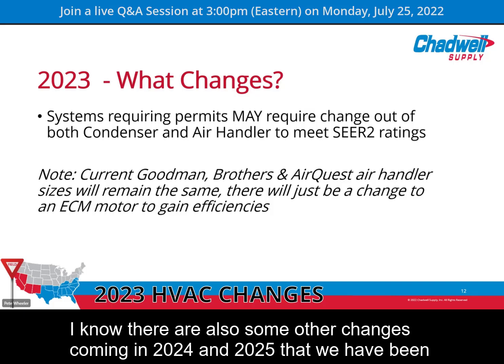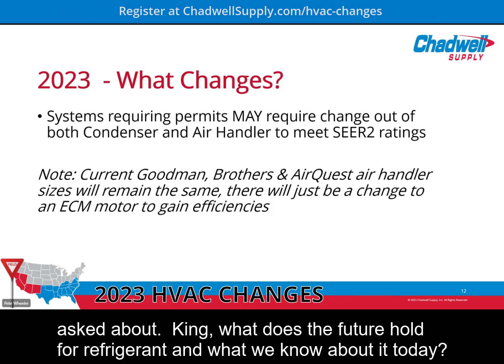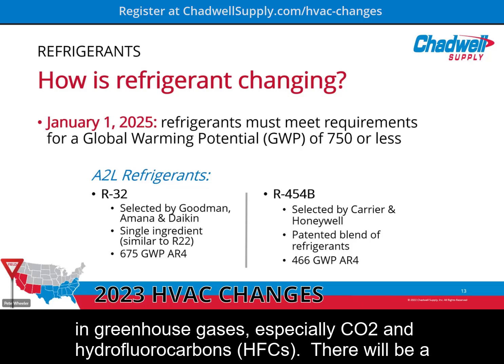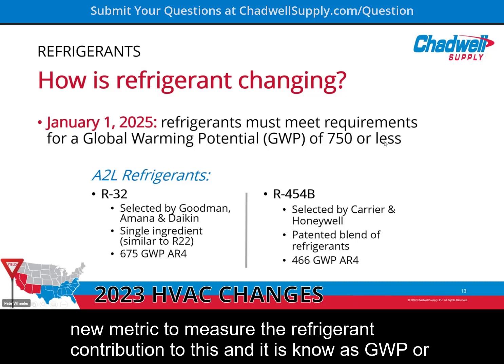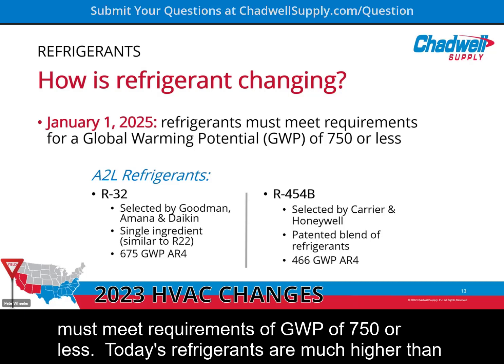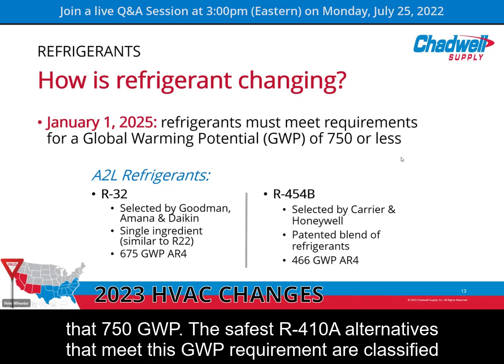So, okay, I know there are also some other changes coming in 2024 and 2025 that we've been asked about. King, what does the future hold as far as refrigerant and what we know about it today? Yeah, so global temperature has been increasing since industrialization with correlation and rise in greenhouse gases, especially CO2 and hydrofluorocarbons or HFCs. There will be a new metric to measure the refrigerant contribution to this, and it is known as GWP or global warming potential. On January 1st, 2025, all refrigerants coming out of the factory must meet requirements of GWP of 750 or less. Today's refrigerants are much higher than that 750 GWP.